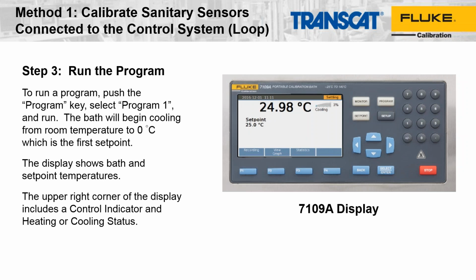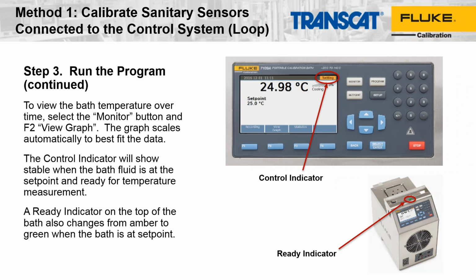the bath will show the temperature set point it's on currently, the actual temperature inside the tank, and then also how much cooling or heating is being required to ramp up or maintain the temperature. There's also a light on top, just above the controller, called the ready indicator, and when the bath sees that it's at sufficient stability, it will turn on this light to let the operator know that they can go ahead and take measurements. As the program is running, you can use the monitor button and pull up a graph if you want to see what the temperature is looking like inside the tank.